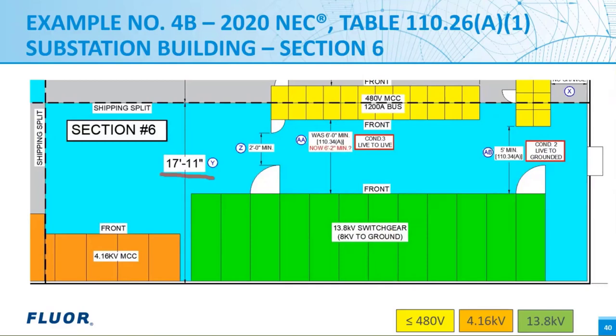However, we must remember what was mentioned earlier also about the possible intermediate roof supports of every one of these minimum clearances we've been looking at, entering into and out of these workspaces. The building fabricator is going to need to pay a lot closer attention to the location of these supports and be aware of the restrictions that may happen once the equipment is put in. And in cases where you have the house builder, the building fabricator, and the building integrator that actually places the equipment and does all the wiring, where they're two separate companies, then there will need to be a lot more coordination between the placement of the roof supports and the equipment.